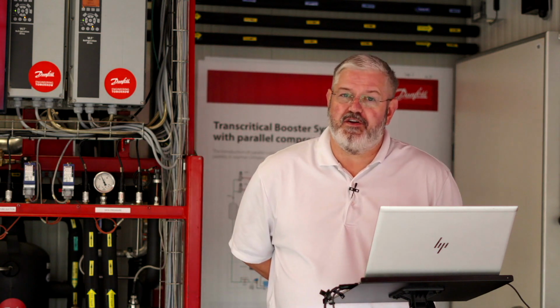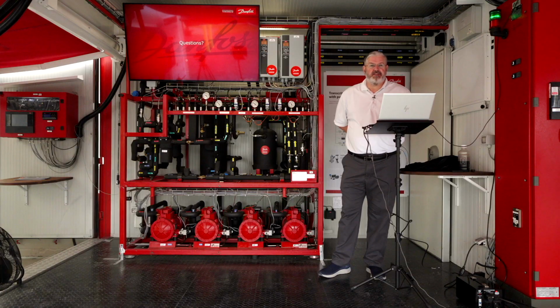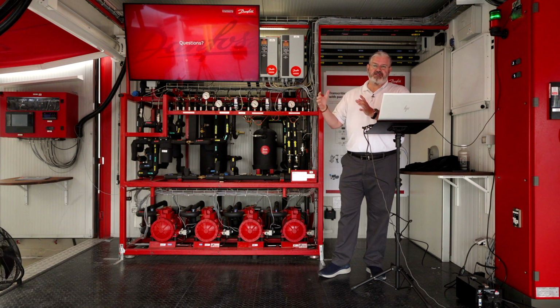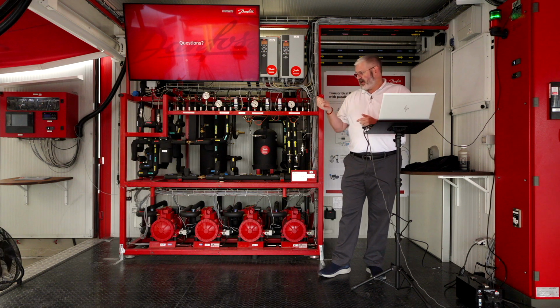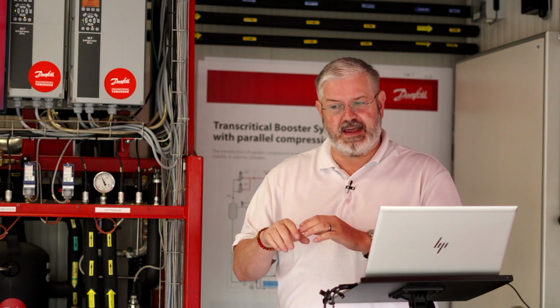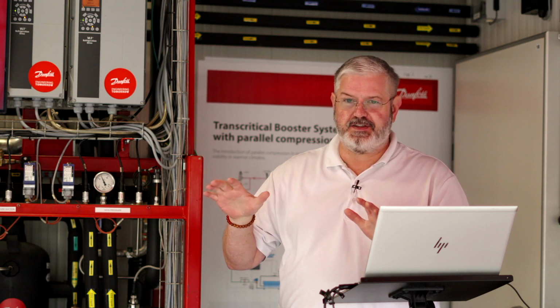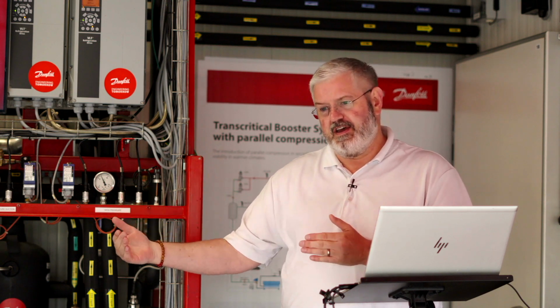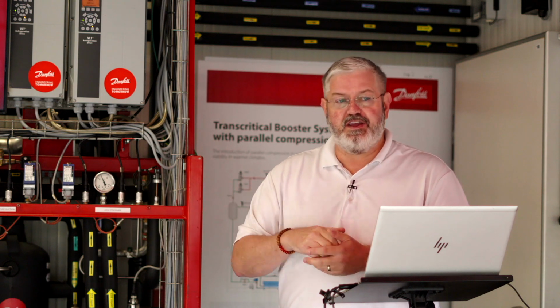So I have a question. If the system is completely empty, how do you get it above 100 pounds? And this would be in reference to, say, system charging or service work where you had to pull a vacuum on the system. CO2 comes in two cylinders. You can get a vapor tank, which has no liquid in it, and then you can get a liquid cylinder that's stacked with liquid, and the takeoff is a siphon tube that goes to the bottom of the tank. If you had a system below 100 pounds, you would use a vapor tank to charge it above that. And again, you'd want to make sure valves are open throughout the entire system. Everything you evacuated needs to be accessible all the way back to the charging port, and you would use a vapor tank to get it above 100 pounds and then resume charging with liquid.